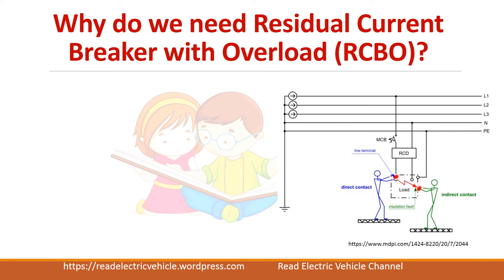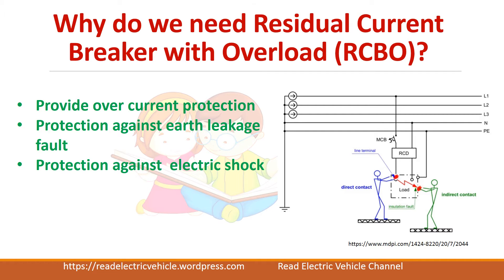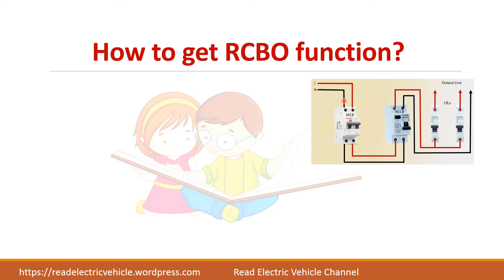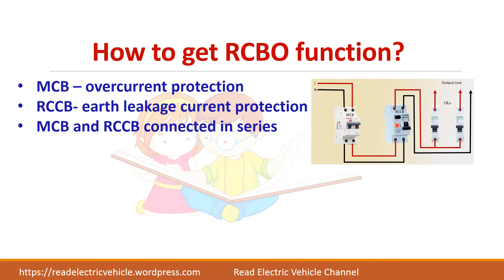So why do we need this RCBO? The RCBO is a device which can provide overcurrent protection, protects against earth leakage faults, and protects human beings from electrical shock. Normally, what is done is an MCB is connected in series with the RCCB. This combination can give you both overload protection as well as detect the earth leakage fault.